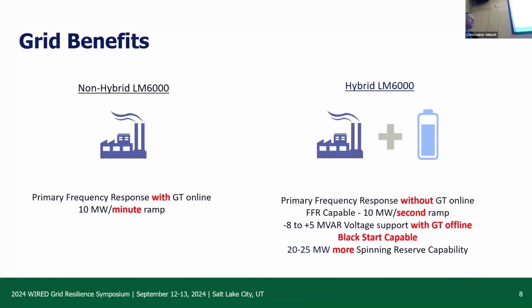Here's how the hybrid looks. It can provide primary frequency response from the battery alone without the gas turbine online. It can ramp the full 10 megawatts in less than a second. In doing that, it's able to provide fast frequency response. So when the tie line sheds, it can add those megawatts in an instant to the grid to help balance the frequency. It's capable of some modest voltage support with the GT offline. It's also black start capable.